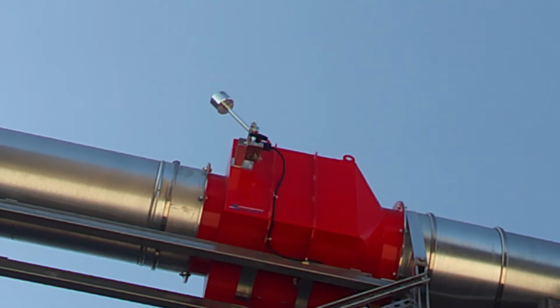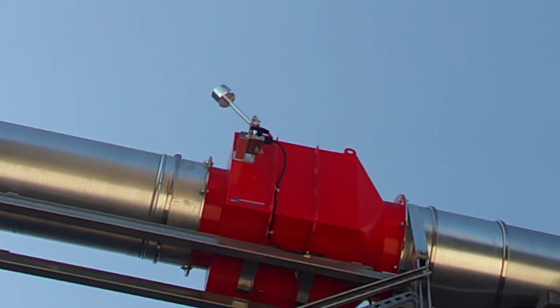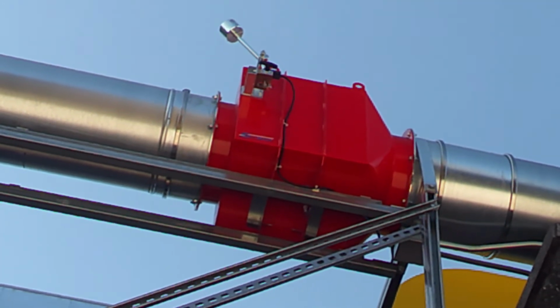That's a sensor, and what that sensor is for, it's a dust level sensor, so that if dust is building up in that control for whatever reason, the airflow is inadequate, or there's a lot of turbulence in there. Dust, which ordinarily in a straight piece of pipe may just go flying along, may end up building up there, and that's not desirable. So that thing will sense that there's dust, and it will show up as a fault. Remember on the front of that box, one said OK and the other one said fault. It should turn that light on, and you have to go out and clean it, which is not that easy.